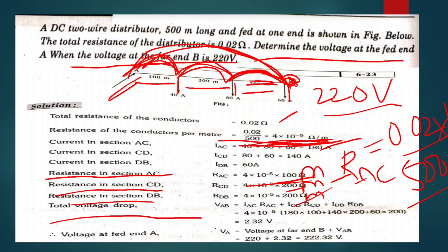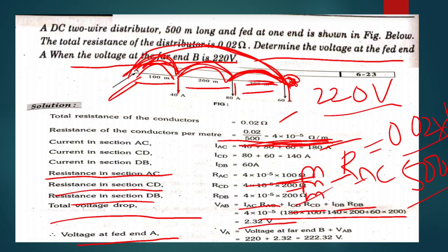Calculating VAC, VAC = IAC × RAC; VCD = ICD × RCD; VDB = IDB × RDB. Adding all voltage drops gives the total VAB. The total voltage at fed point A is VA = VB + VAB = 220 + 2.32 = 222.32 volts. Thank you.